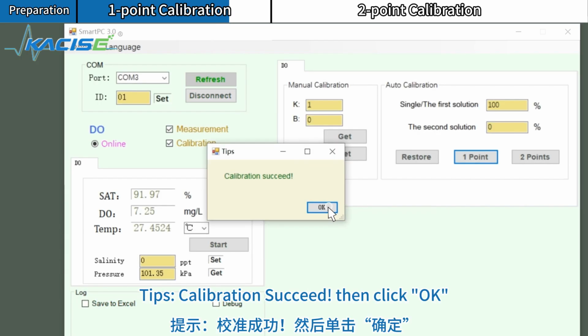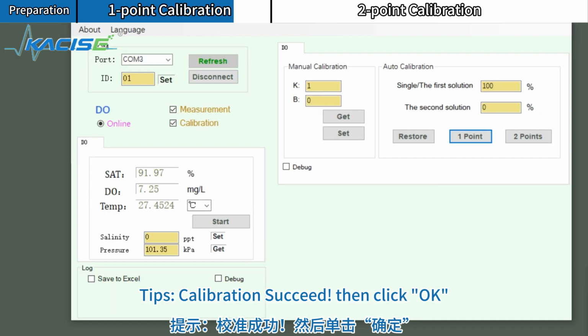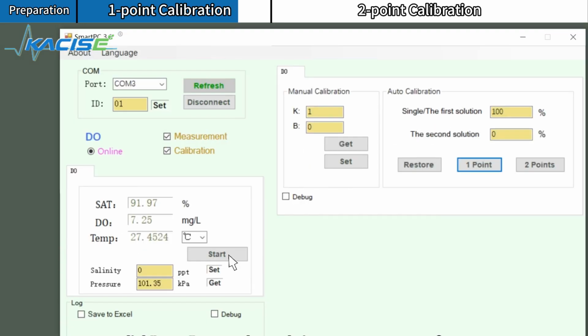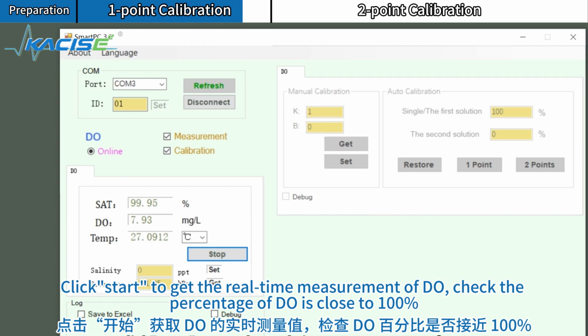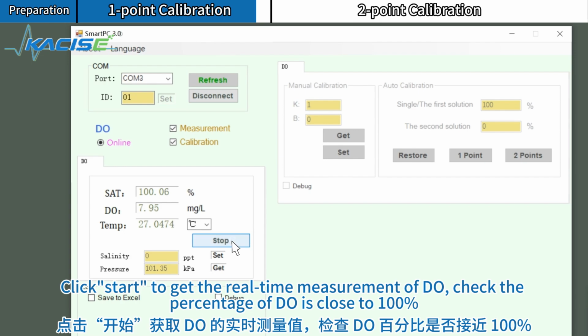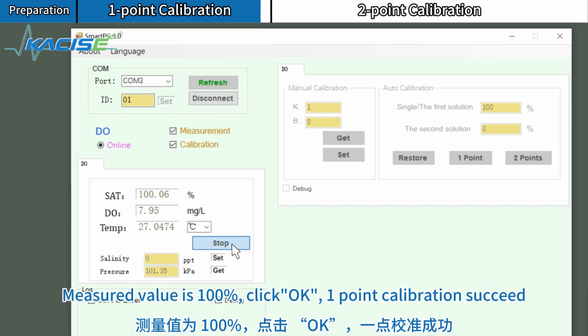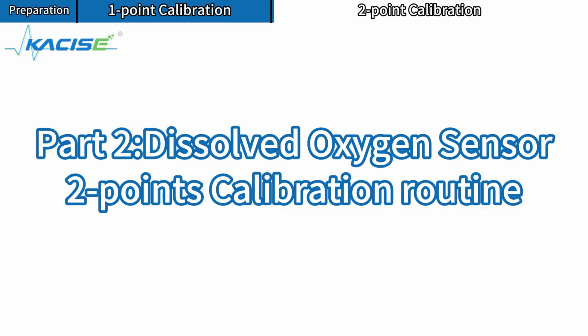Tips: calibration succeed. Then click OK. Click Start to get the real-time measurement of DO. Check that the percentage of DO is close to 100%. Measured value is 100%. Click OK. 1-point calibration succeed.